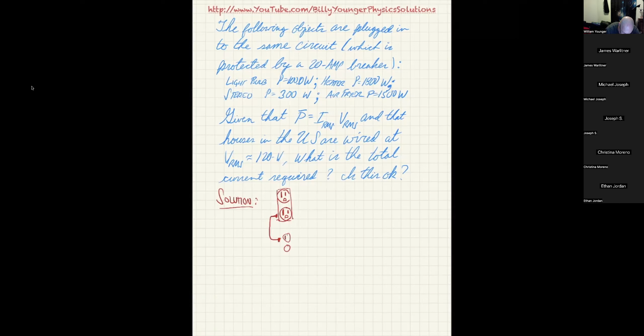But beyond that, let's get rid of this. So what I wanted to show you about this is specifically the fact that these things are actually all wired in parallel. Because what will happen is you'll have, here's another receptacle, you'll have a wire that comes from this side and connects to this side. Okay, and you can imagine that connecting to the long side of the receptacle, and you'd be right, because it's always going to consistently be that. Similarly, you're going to have another wire coming from the short side going to the short side again, like that. And then the next receptacle will go off like this from here to this receptacle, in which case you have a circle, and then you have another wire coming from, say, here going to here.